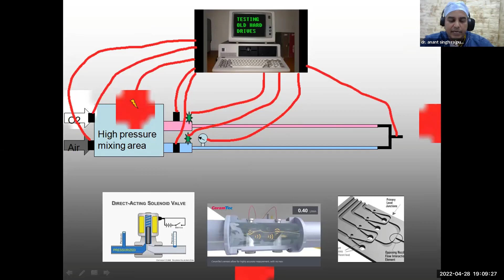There can be an additional proximal airway pressure sensor which we can add. So there are some tubes in which you will see at the Y piece of the ventilator, there is an additional port where you can connect the tubing back to the ventilator. So that is the PAW written there. That is proximal airway pressure. It is more accurate than the pressure sensed by the ventilator from the expiratory limb, right?